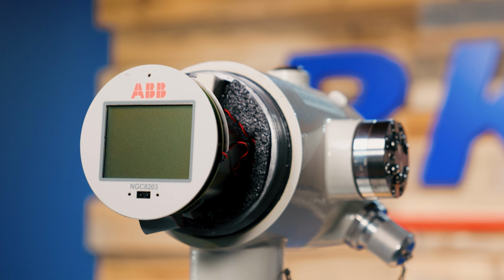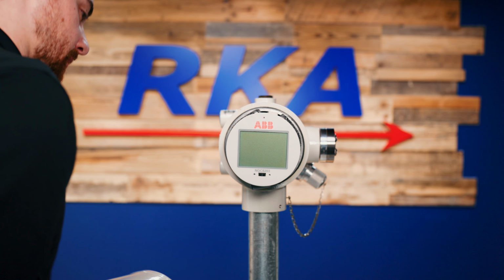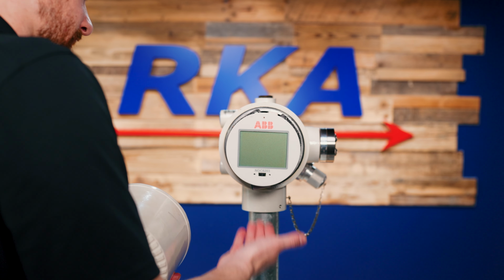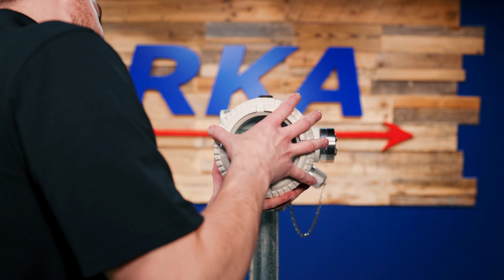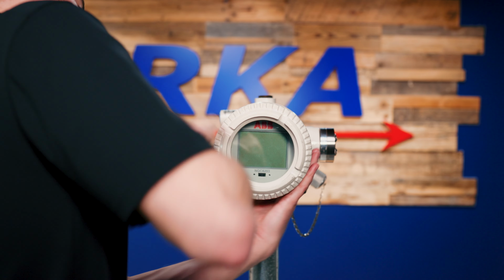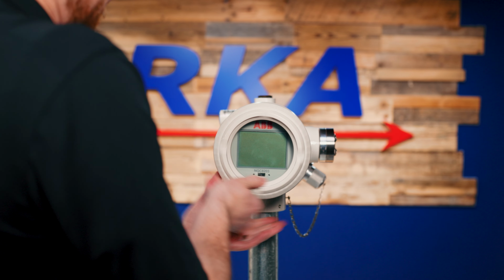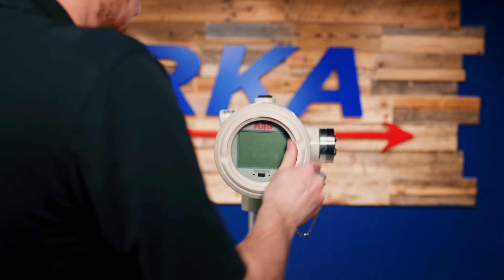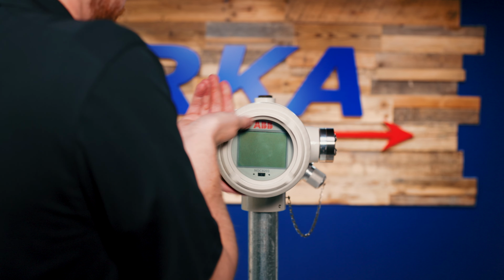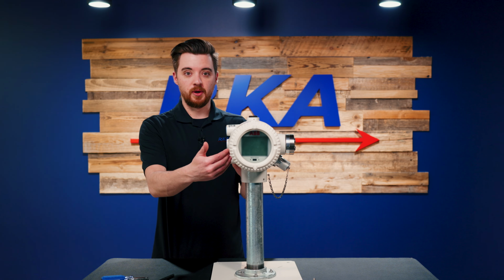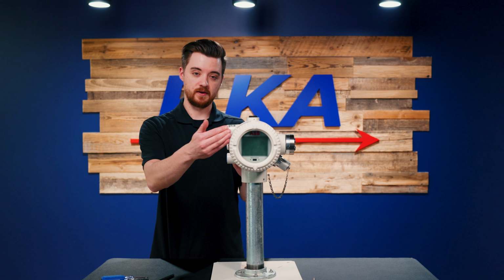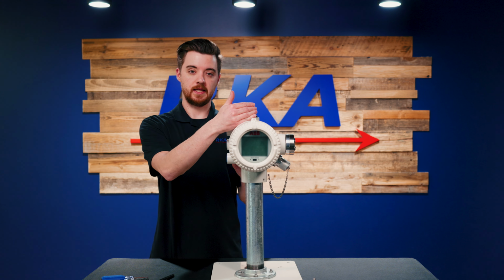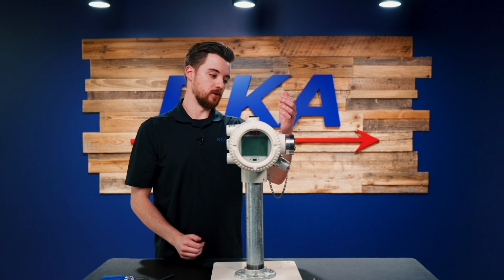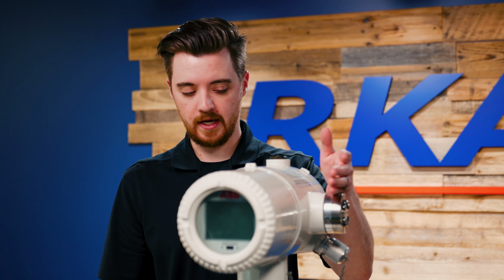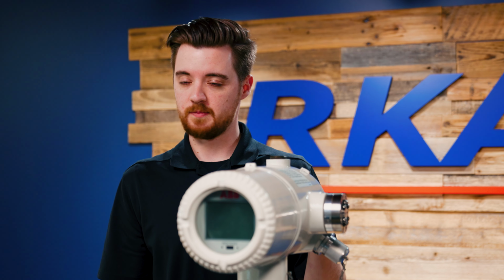Now that all of our cables are installed, we can go ahead and put on our cover, being careful of the ribbon cable as not to pinch it. Now that all the components have been put back into the GC, your cover is back on, you can reestablish the gases moving to the unit, your sample gas, your cal gas, and your carrier gas, and you can resupply power to your GC, and your module replacement has been done.